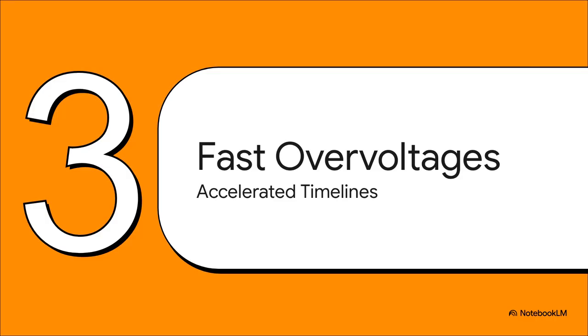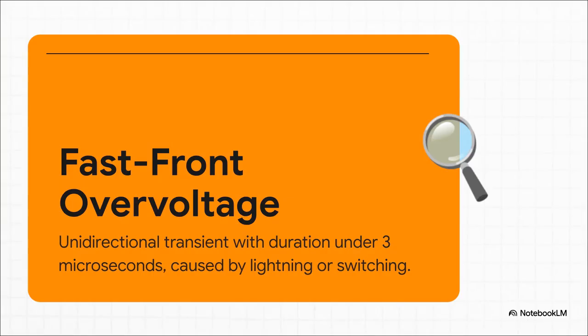Let's move to Section 3 and see how this builds. Fast and very fast overvoltages, accelerating the timeline. A fast front overvoltage is a unidirectional transient with an exceptionally short duration. While SFOs are often tied to that routine switching we just talked about, FFOs are most frequently the result of severe external events, specifically massive lightning strikes or operations at a disconnector switch.